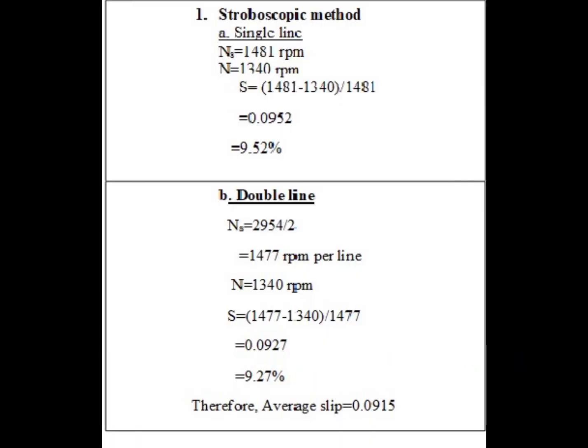After finding the speed of the motor using the double line and the single line stroboscopic meter method, we were able to get an average slip of 0.0915.